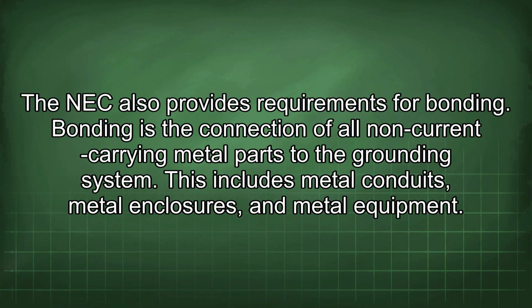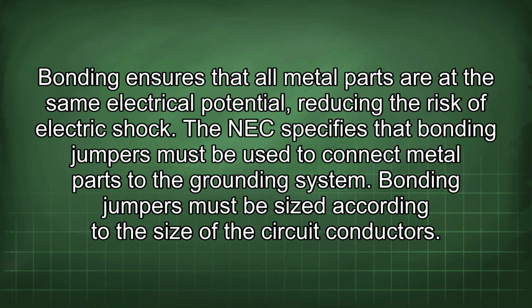The NEC also provides requirements for bonding. Bonding is the connection of all non-current carrying metal parts to the grounding system. This includes metal conduits, metal enclosures, and metal equipment. Bonding ensures that all metal parts are at the same electrical potential, reducing the risk of electric shock.